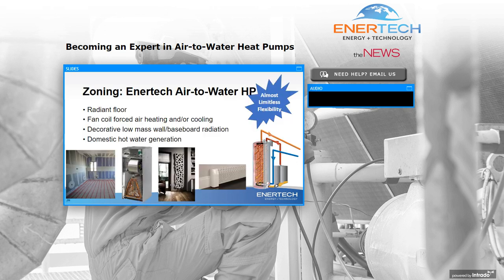As Tim mentioned, zoning is just great with hydronic systems. And up to this point, we had some choices in the market. You know, water-to-water heat pumps with geothermal certainly is a choice that Enertech already has. But if we're looking at hydronic with boilers, we don't get cooling. So the one opportunity we have with zoning and an air-to-water heat pump is we can still do all the hydronic systems that we might have done with a boiler. We do have to watch water temperatures, and I'll get into that here shortly.